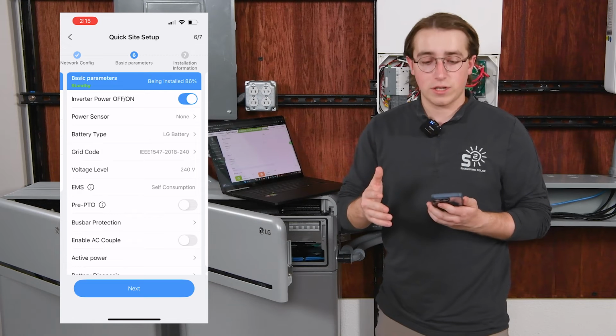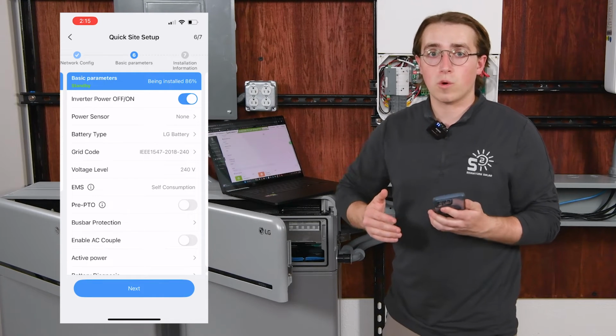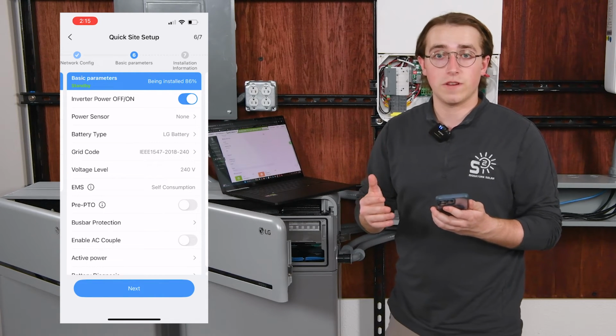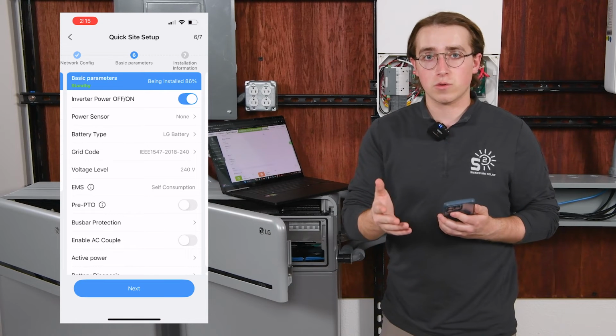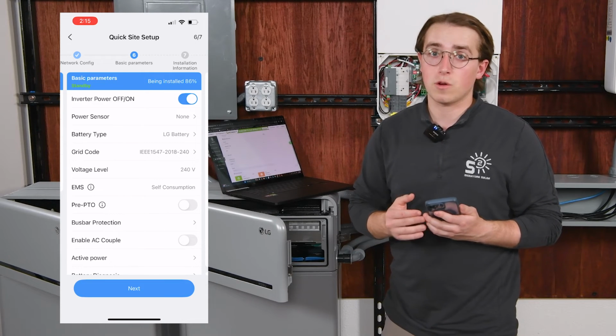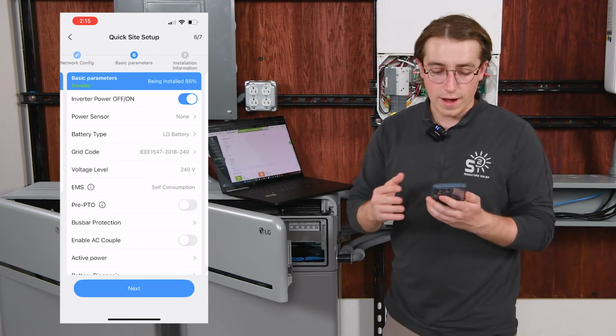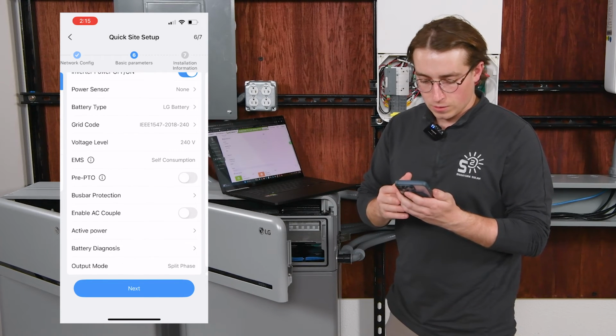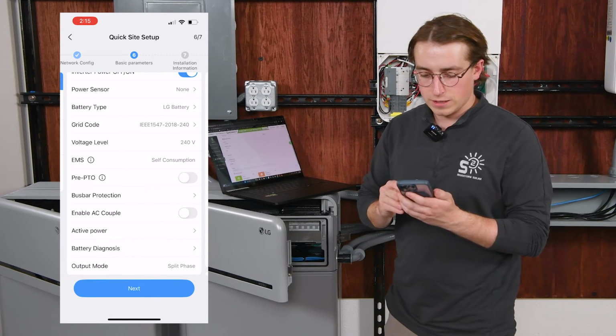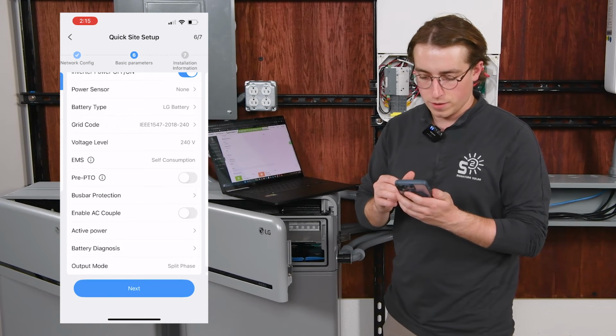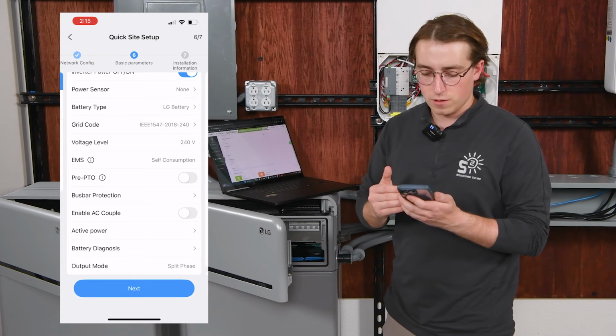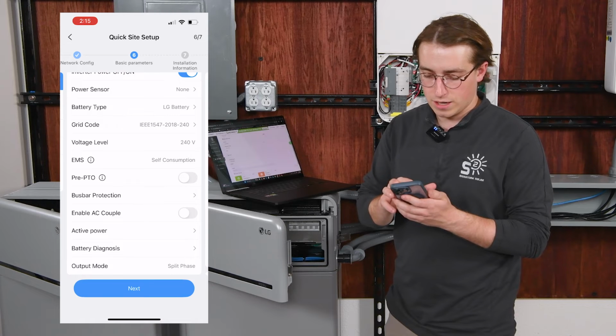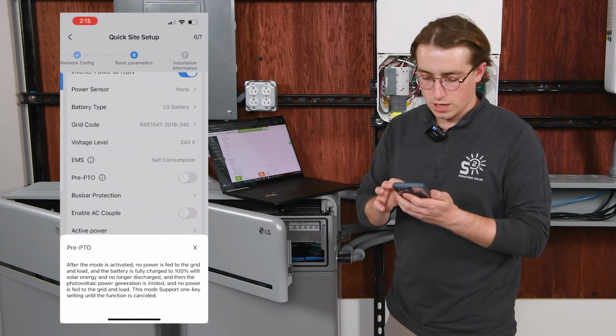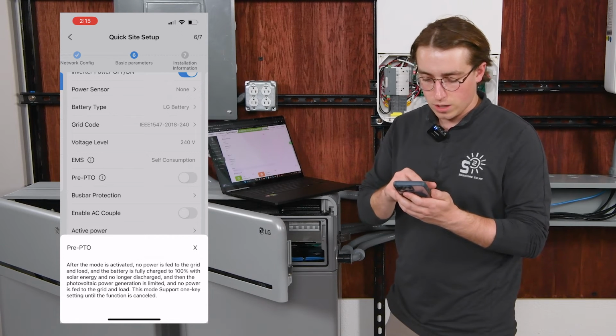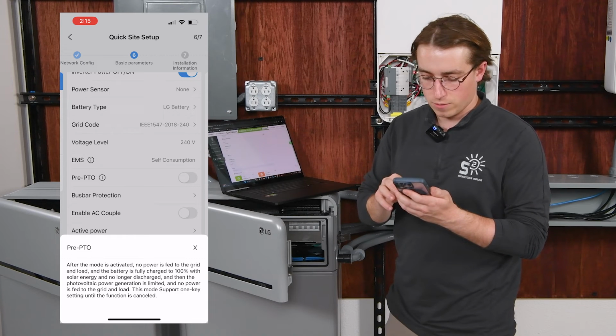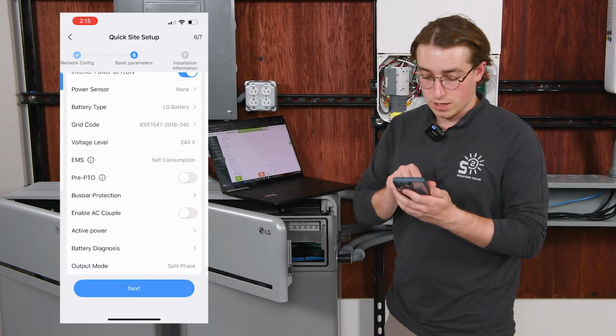Now, right under Battery Type, you'll see Grid Code. Where we're located, we'll use IEEE 1547, but this grid code depends on the region that you're in, so it may be different for California or Hawaii. We see that our output mode is set to split phase, and our voltage level is set to 240. There are some other settings on here, like Pre-PTO and EMS, and if we hover over or click the Information button, we can see some more information there. Next, we'll click the Next button.